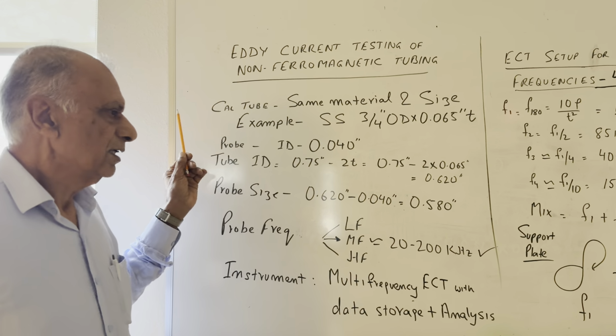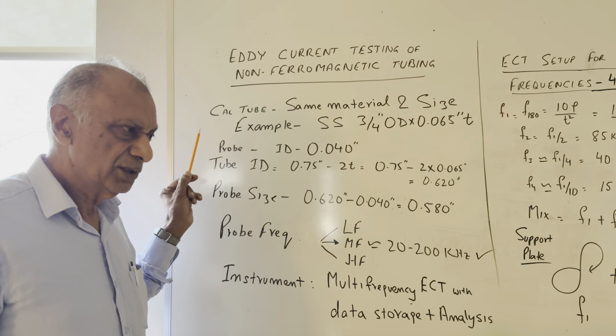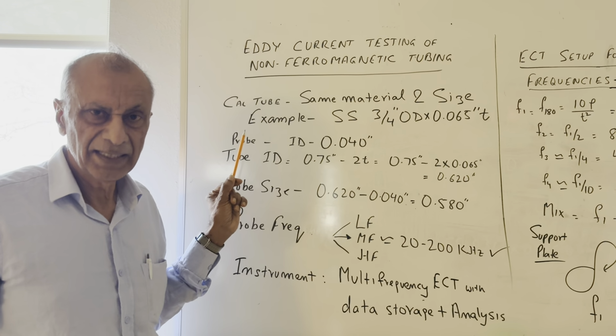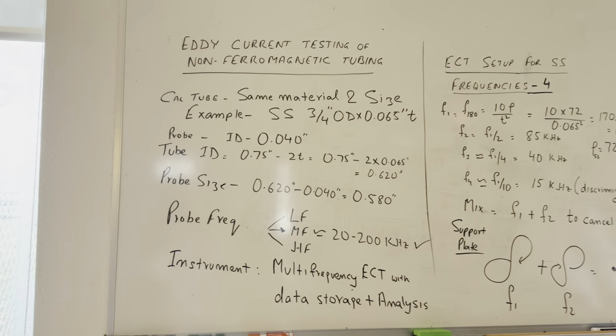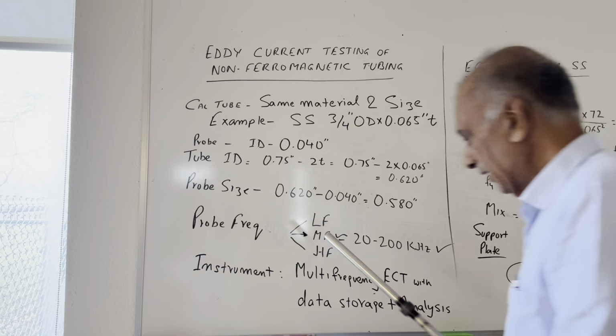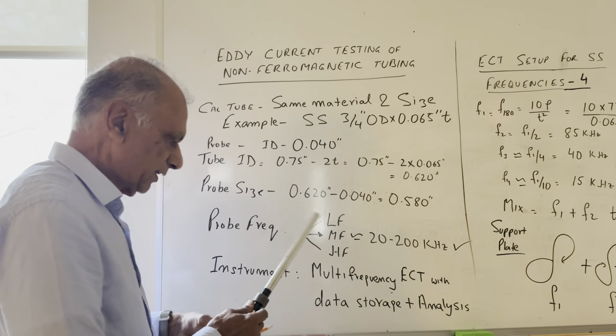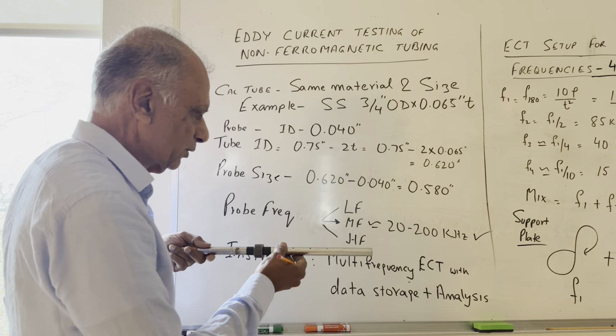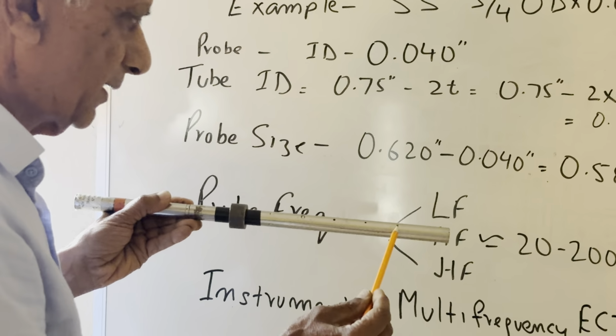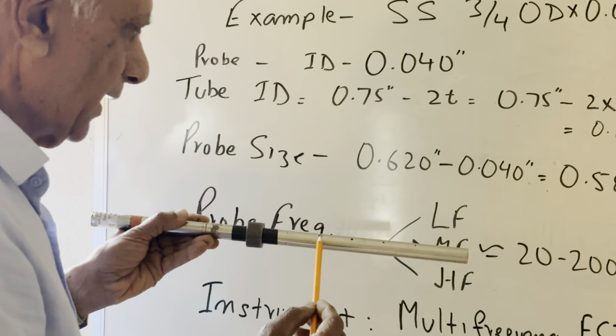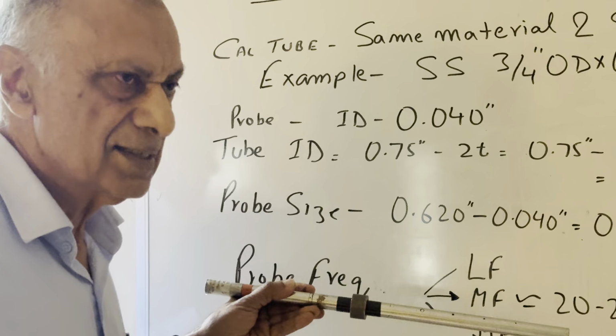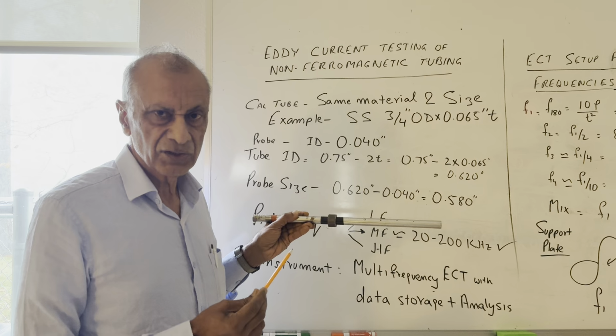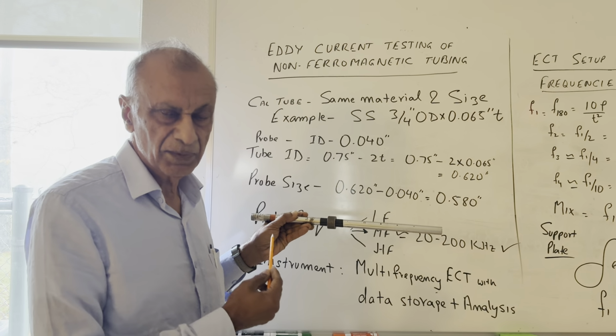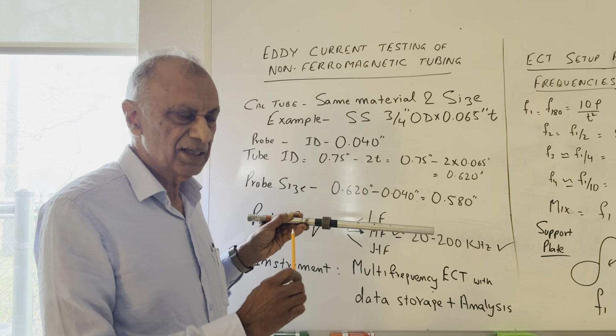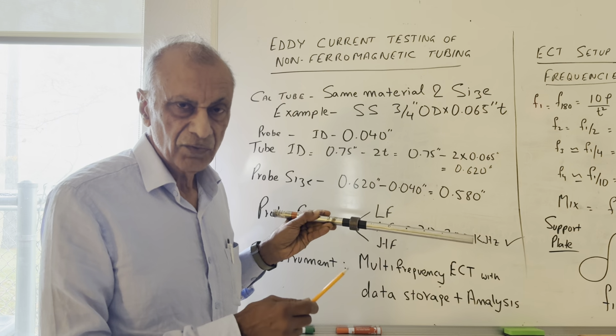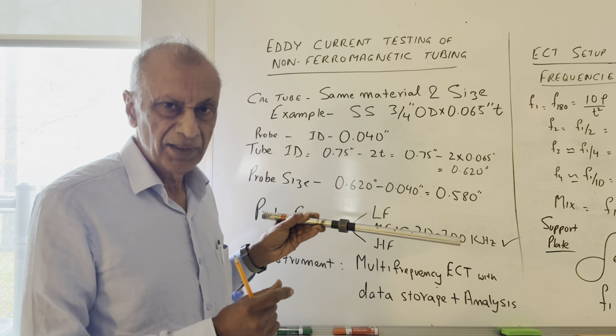First thing, when we start, we have to make sure that we have a calibration tube, which has to be the same material and the same size. So I have this calibration tube which is 3/4 inch OD and 0.065 inch in thickness, so it has to be the same. And this calibration tube should have those 5 holes, which are the 100%, 80%, 60%, 40 and 20%. These are flat bottom holes, and the size of these holes is given in the ASME Section 5. The depth is given, and the diameter is given in such a way that it produces the same amplitude from the holes. So as the holes get shallow, the diameter gets bigger.